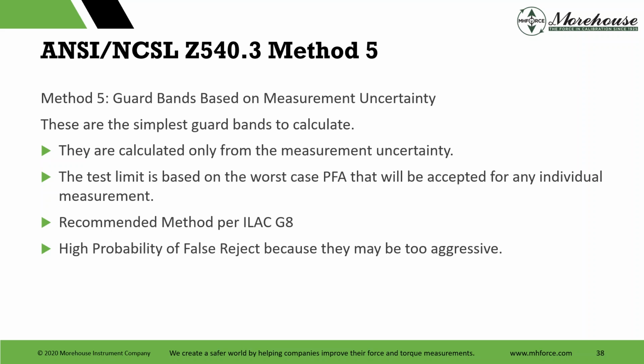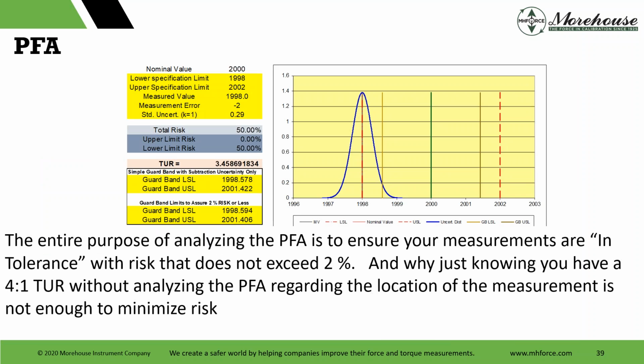And then in ANSI Z540.3, guard bands are based on measurement uncertainty. Method 5 is the simplest guard band to calculate. The test limit is based on the worst case PFA that will be accepted for any individual measurement. Recommended for ILAC G8. High probability. The downside is that there's a very high probability of false reject because it may be too aggressive. Meaning you take the measurement uncertainty into account, and then the lab that you sent your item to for calibration is adjusting it frequently. And the entire purpose of analyzing the PFA is to ensure your measurements are in tolerance with risk that does not exceed 2%.